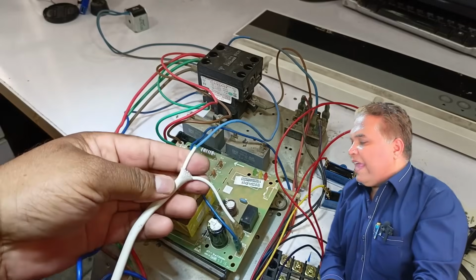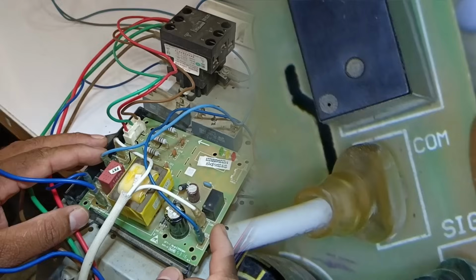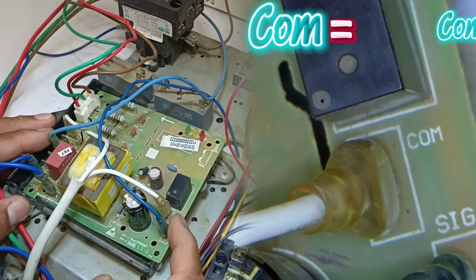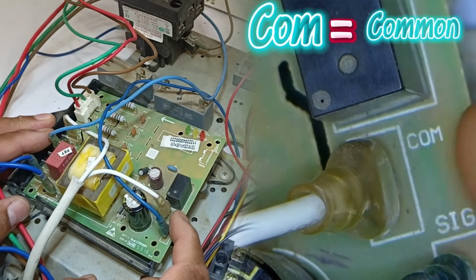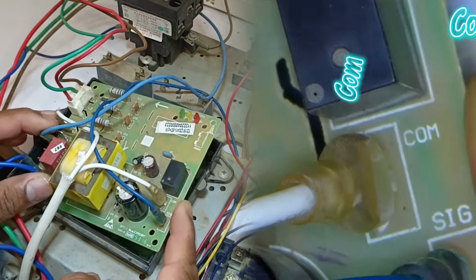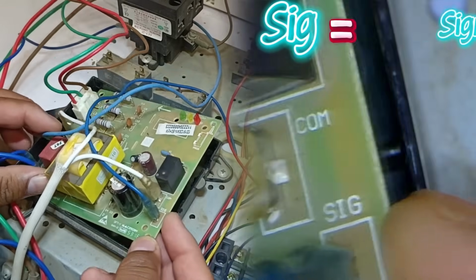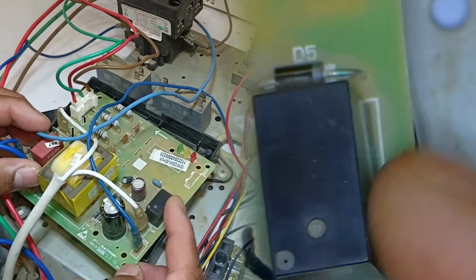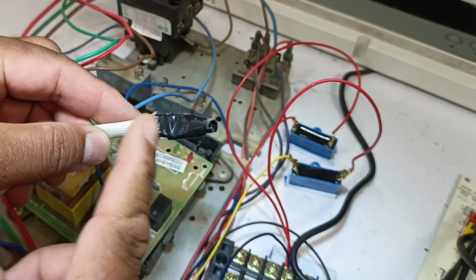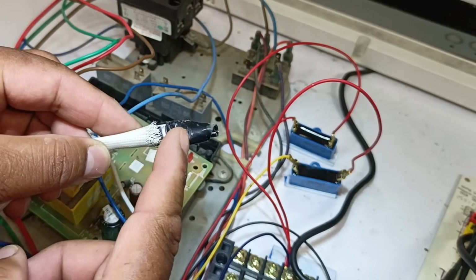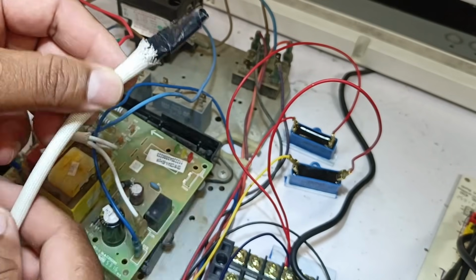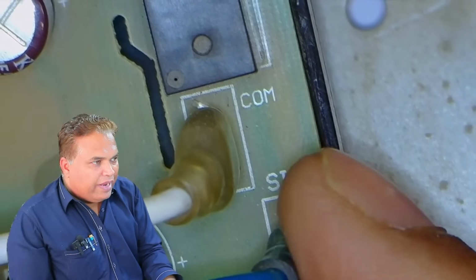Now, of these 2 wires, one is connected to N1 and the other to common. The neutral comes to this common point, and alongside it, you can see it is marked SIG, signal. A relay is installed here, which is responsible for switching this signal. Now, what happens is, between these 2 points, the high-pressure switch maintains continuity. The neutral from N1 reaches this common point.